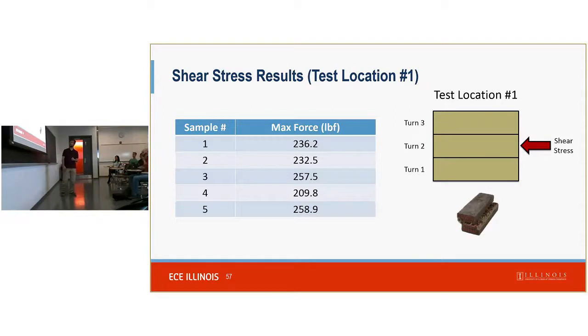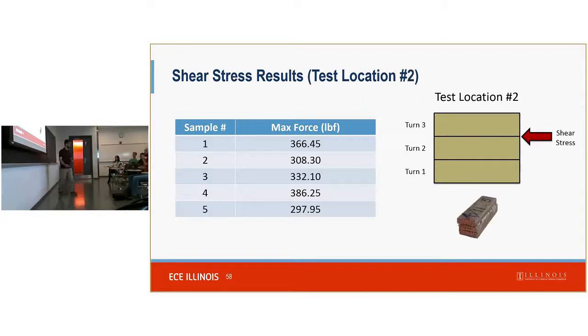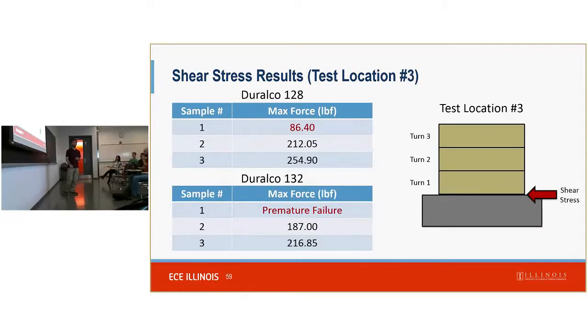And we found when testing through the middle of one turn, so each winding has 3 turns stacked on top of each other, and when testing through the middle of one turn for the force application, we were getting forces above 200 pounds force, which is well above the minimum required. We found even higher strength between the turns, and that is presumably because the resin doesn't perfectly penetrate within the wire within one turn, but between turns there's consistently a really good layer of resin, and the resin is stronger than the copper wire.